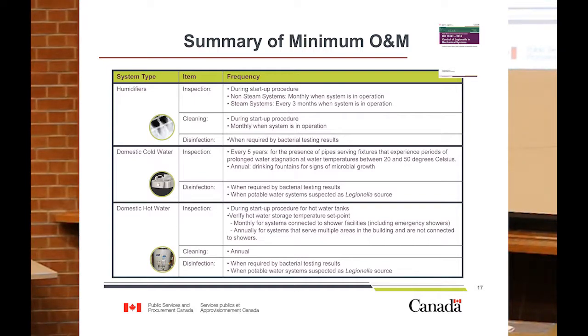So there would have been an assessment when the LBCMP was first created, and then we want to reevaluate those on a regular basis. On the domestic hot water system side, we're focusing on making sure that the water is hot. So checking the set points of the tanks to make sure they haven't changed, and also checking the water temperature coming off of those systems and your recirculation lines to make sure it's out of the growth temperature range.